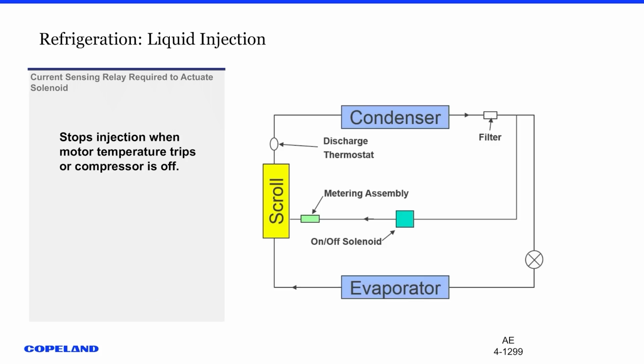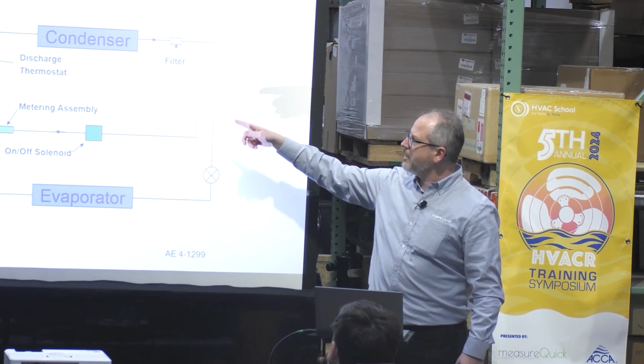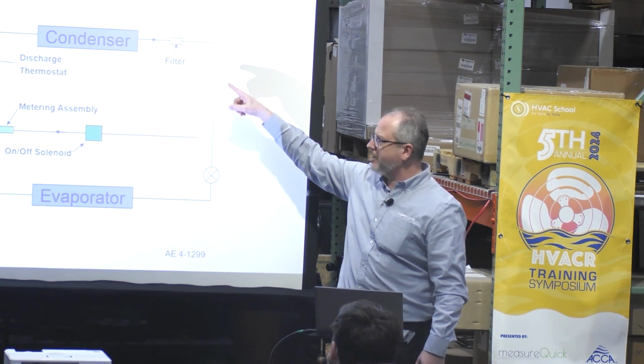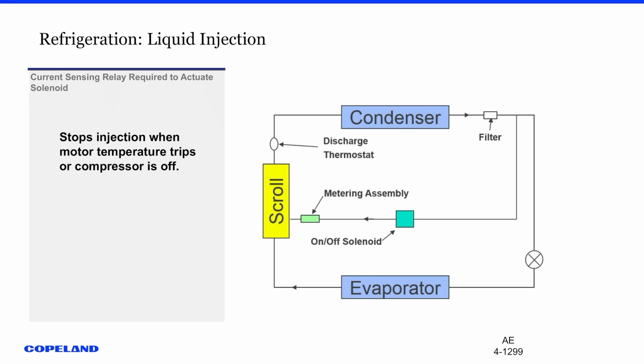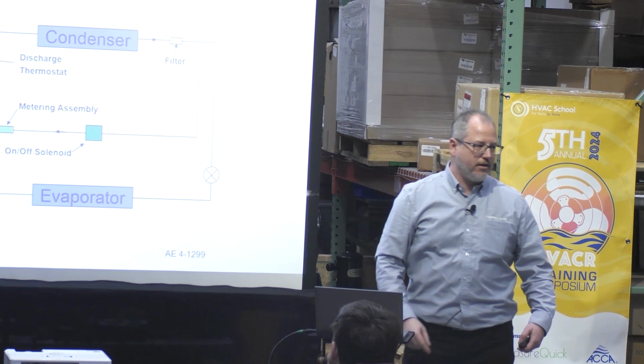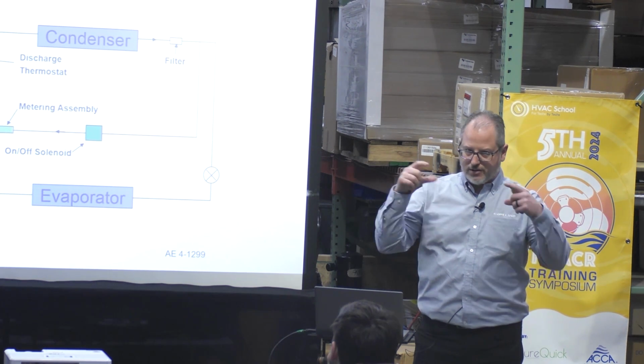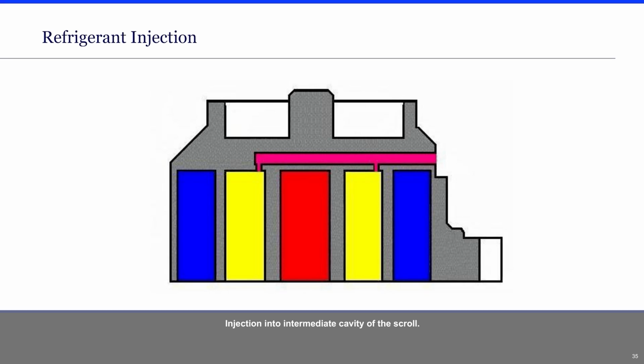So with injection, all we're doing is we have our normal system. We have our compressor going to our condenser, going to our metering device, to our evaporator, back to our compressor, right? Now for injection, we're just going off the liquid line here, and we're going through a solenoid, because anytime that compressor's off, we don't want that refrigerant to migrate into our compressor, right? And then, so whenever we need this, the system's on, that's going to be open, and then we have a metering device, okay? And that's bringing the refrigerant into our scroll set. And that little red pinkish line right there shows where it's bringing it into that scroll set to cool it down, okay?